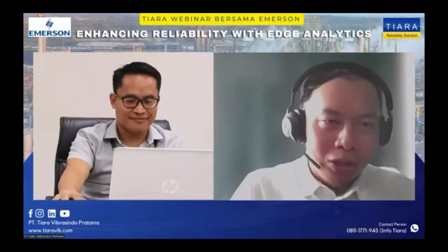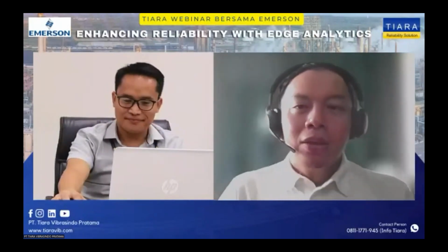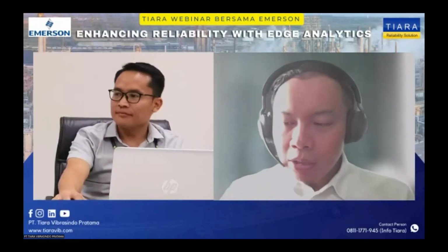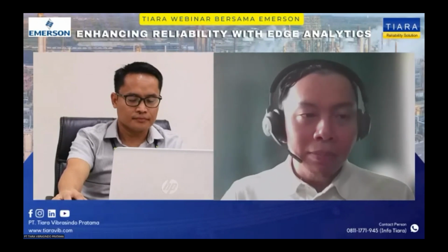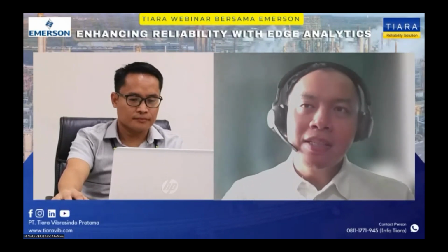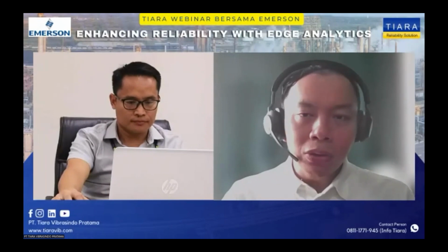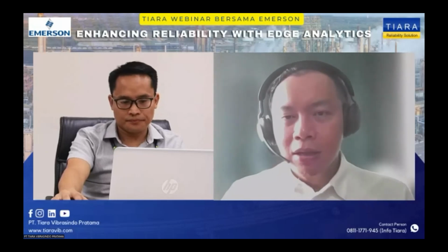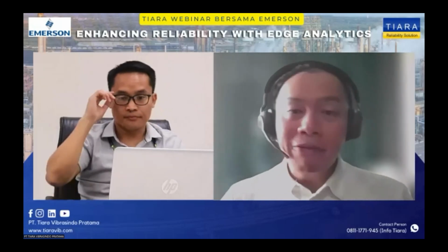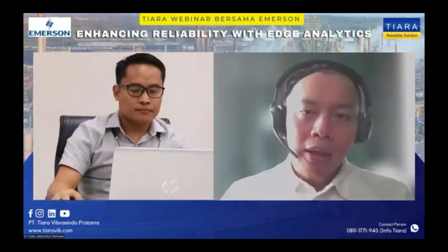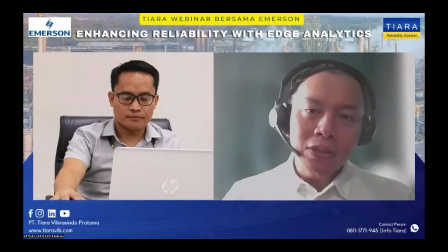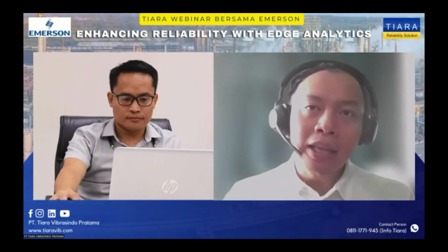Okay. Thank you, Pak Siddiq, for the question. The simple answer is no. You will still need your portable analyzer. As I mentioned in the beginning of my presentation, the portable analyzer is still a very important tool, even when you're talking about the new way of monitoring your assets. You need it, for example, to verify the data and verify whether the fault is there. The added advantage of AMS 2140 is that it's also a corrective tool. You can also use it to do your balancing, and then you can get the output from there easily.